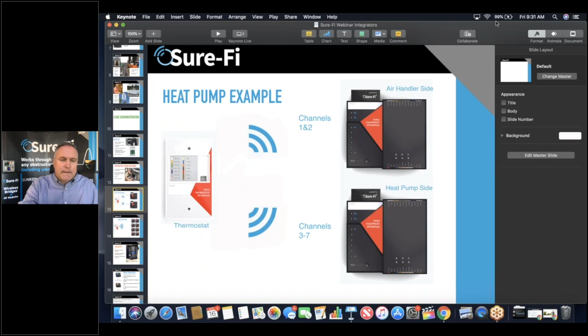Or say you have a bunch of rooftop units in a gym or whatever, and you want to control them off a single thermostat. Or in this case, if you have a bunch of sensors in a BAS system. This shows one of the setups that we did. We have our analog I/O, connected in there to what looks like a Vicon expansion port for analog I/O. Basically, all the sensors and all of the occupation triggers, or whatever kind of sensors you've got out in the building, can come into a single location.